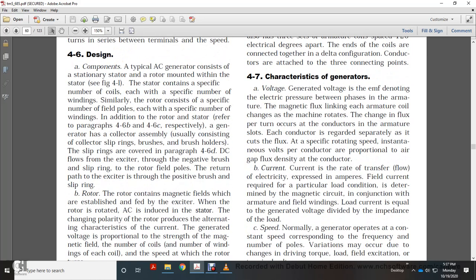All right, 4.7, the characteristics of the generator. Voltage generated is the voltage of the EMF, denoting the electrical pressure between the phases of the armature. The magnetic flux lines cut the armature coil as the machine rotates. The voltage in each conductor of the armature slot is regularly separated, and at constant flux and rotating speed, the instantaneous volts per conductor is proportional to the air gap flux within each conductor.